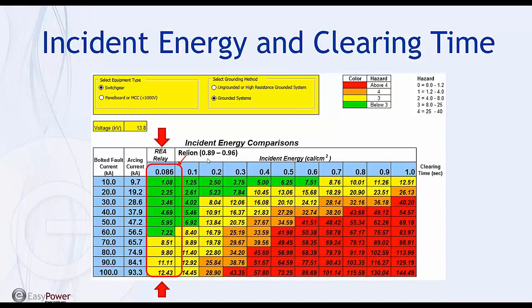The advantage with the REA, of course, is you have loop sensors instead of point sensors. And if the fault current's high enough, depending on the situation, you may want to go with the REA. I think the REA is the best way, just because of the sensing. But ReliOn is a pretty good choice too, to have it built in. So you're certainly going to have a lot more protection than if you didn't have arc flash protection at all.